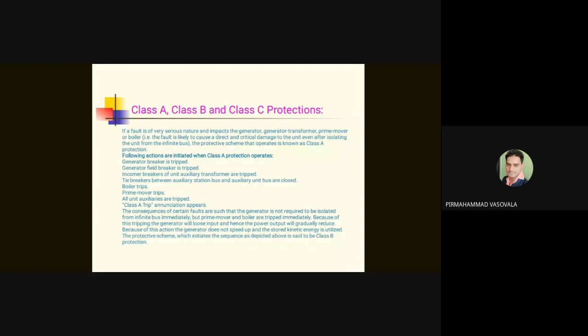Therefore, if there is a fault in the generator transformer, that also is equivalent to a fault in the generator. Similarly, there are two unit auxiliary transformers, or one unit auxiliary transformer, as the case may be. The unit auxiliary transformer is feeding all the auxiliaries of the generator.